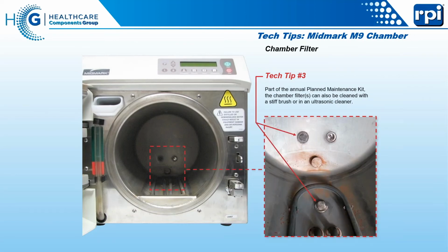Okay, so inside the chamber, part of the annual PM kit again, we have some filters. We don't want all the crud from their packs getting into our nice clean machine. So we want to try to isolate that with these filters. They can be ultrasounded if the machine needs to be cleaned off cycle, but they're basically there to prevent paper or fiber material coming off the packs from getting into the valve streams.